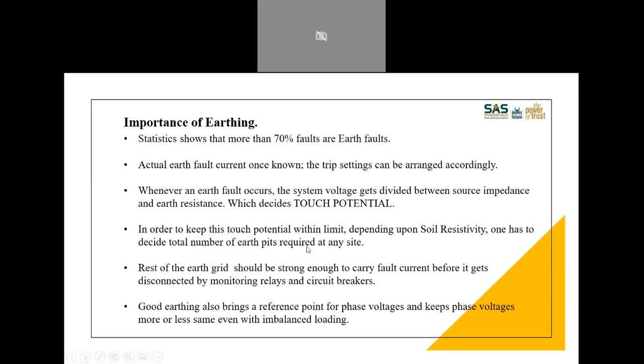Earthing itself can be a 2 hour webinar or even a 1 full day webinar. So we'll not go into details of this, but the basic points are these: how many earth pits you should have starts from the short circuit current. Next is what your soil resistivity is. Third is what the standards related to touch potential are. Based on that, these earth pits are supposed to be created.